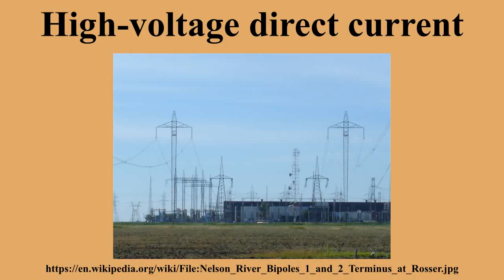Overhead line systems. The capacitive effect of long underground or undersea cables in AC transmission applications also applies to AC overhead lines, although to a much lesser extent. Nevertheless, for a long AC overhead transmission line, the current flowing just to charge the line capacitance can be significant, and this reduces the capability of the line to carry useful current to the load at the remote end. Another factor that reduces the useful current carrying ability of AC lines is the skin effect, which causes a non-uniform distribution of current over the cross-sectional area of the conductor. Transmission line conductors operating with direct current do not suffer from either of these constraints.